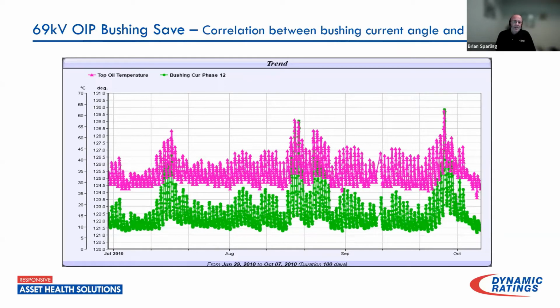And here's the case of correlation between the bushing current, phase angle, and temperature as well. So it all points to, in this case, a dissipation factor problem inside the bushing, which cannot be fixed, of course. In service, it has to be replaced. The point is, you have the warning that something's going wrong, take the outage, test it, repair it, replace it, I should say, and put it back in service.